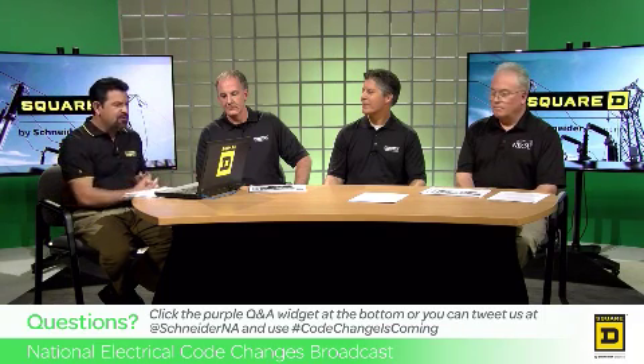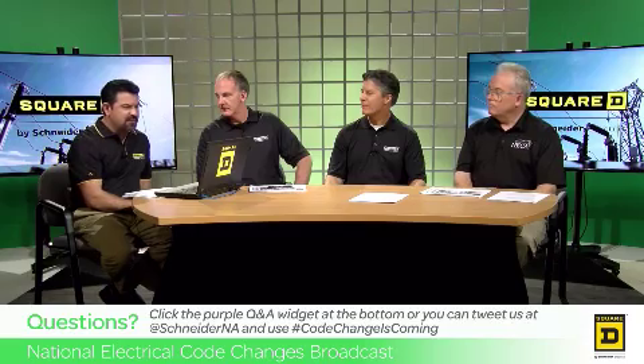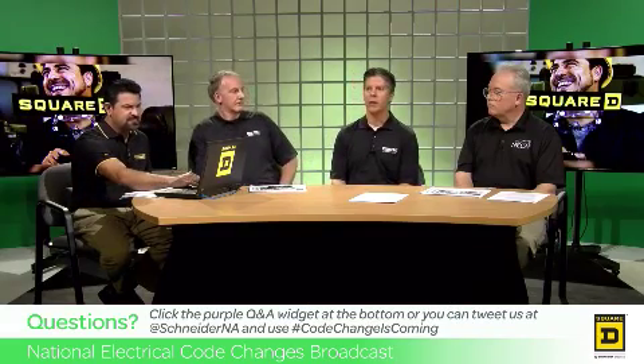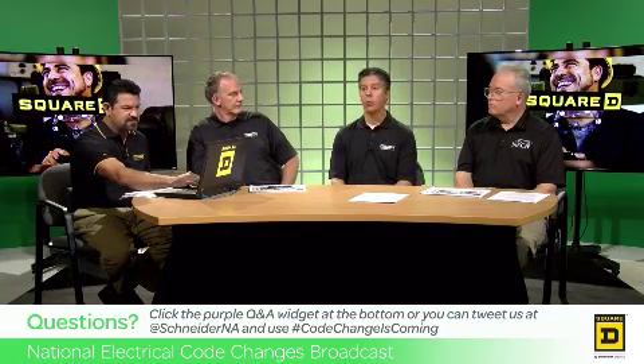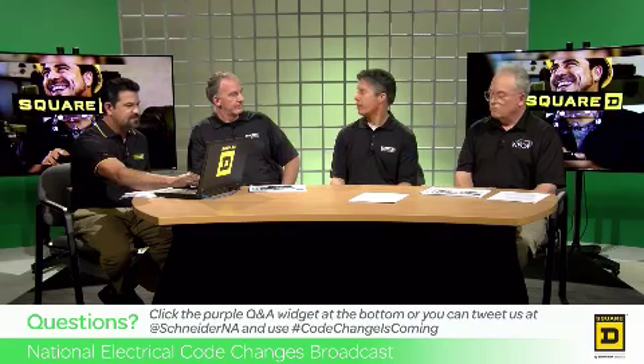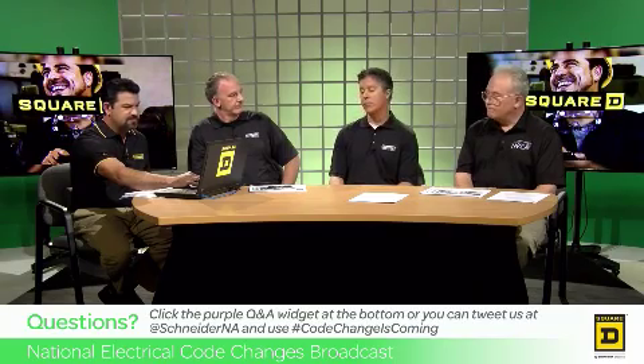In regards to the new arc flash hazard marking, do I need to place this marking on all panelboards being installed on a project? So the new change in 110.16 really applies to the service equipment. Right. Mm-hmm. So it's a good idea, right, to know your arc flash hazard at all your panels. Okay, great.